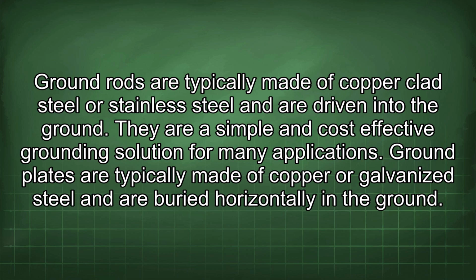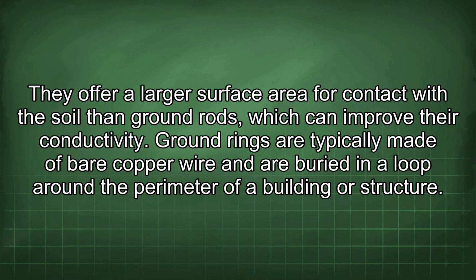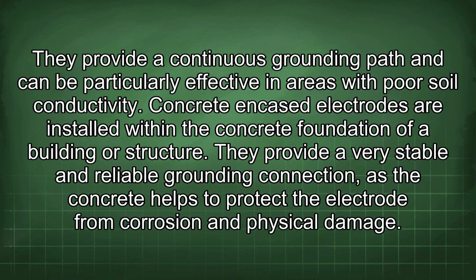Ground plates are typically made of copper or galvanized steel and are buried horizontally in the ground. They offer a larger surface area for contact with the soil than ground rods, which can improve their conductivity. Ground rings are typically made of bare copper wire and are buried in a loop around the perimeter of a building or structure. They provide a continuous grounding path and can be particularly effective in areas with poor soil conductivity.